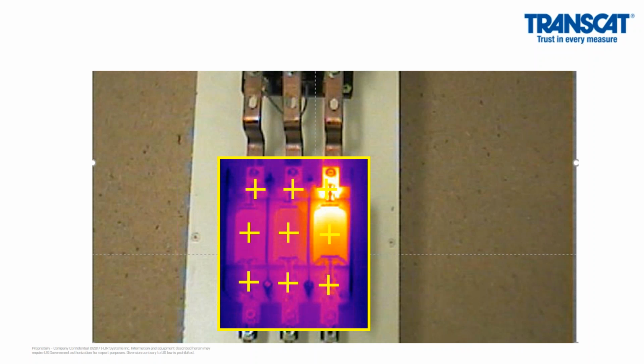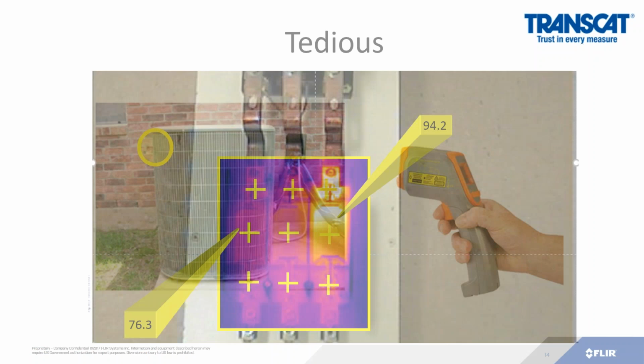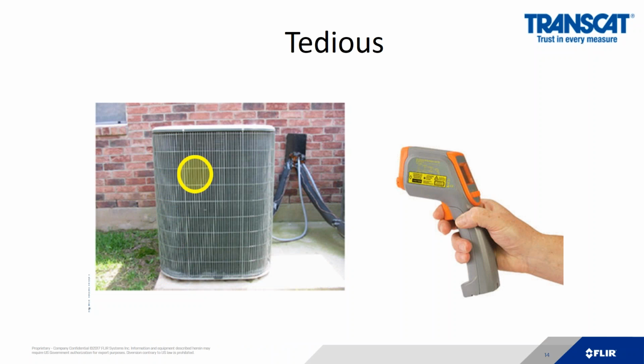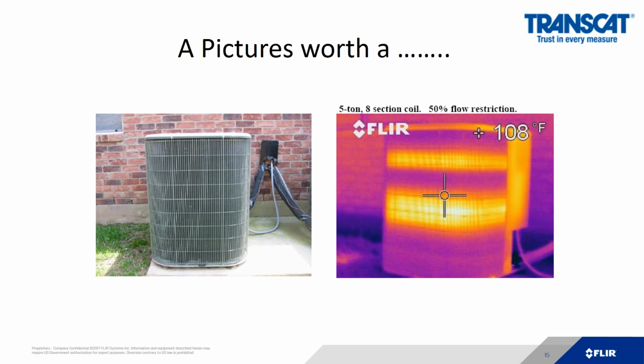With a thermal camera, on the other hand, a picture's worth 1,000 words. I clearly see, in this case, C phase is warmer than A and B. So from that instant, I would then take more additional information that the camera can provide me. We can easily see not only the temperature of the 2 points, but also the delta that we would have here is roughly 18 degrees. There are many building applications that we will get to later on in the presentation. If I was looking at this example, I'd have to scan up and down very tediously to see if there was a problem, where with an infrared picture, I can clearly see if there is a problem. As in this case, this 5-ton, 8-section coil has a flow restriction, and I can see a thermal hotspot across the middle of it and in the upper 80% of it.